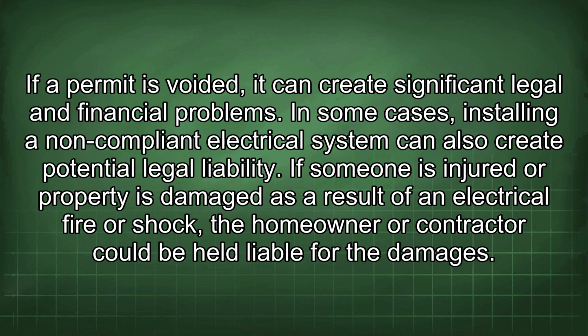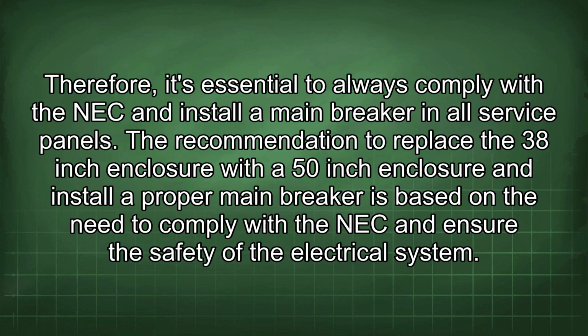In some cases, installing a non-compliant electrical system can also create potential legal liability. If someone is injured or property is damaged as a result of an electrical fire or shock, the homeowner or contractor could be held liable for the damages. Therefore, it's essential to always comply with the NEC and install a main breaker in all service panels. The recommendation to replace the 38-inch enclosure with a 50-inch enclosure and install a proper main breaker is based on the need to comply with the NEC and ensure the safety of the electrical system.